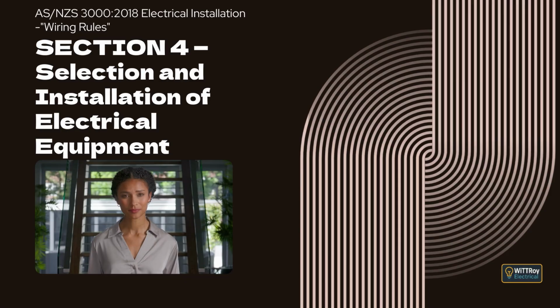Clause 4.7.1 Switching device. This clause explains that a fixed or stationary cooking appliance with an open cooking surface that uses electric heating must be provided with a switch that operates in all active conductors, and that this switch must be mounted near the appliance in a visible and readily accessible position. It explains that this requirement does not apply to enclosed cooking appliances such as built-in ovens or microwave ovens. In New Zealand only, where an appliance has an open cooking surface that uses both gas and electricity, the switching device must operate in all active conductors. It explains that a single switch may control associated cooking appliances located in the same room.